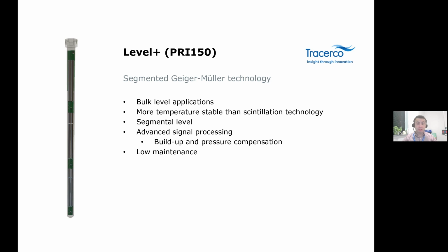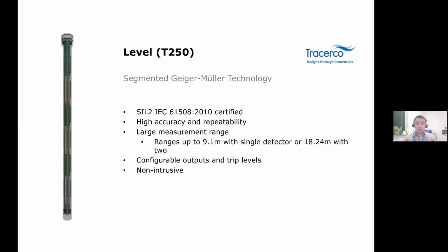Using Tracerco patented technology, the PRI 150 is a breakthrough in level measurement. Unique processing algorithms provide unparalleled insight into the vessel operating condition, monitoring what occurs in the vapor space, allowing extended deposition to be identified. The next generation of our Level Plus includes a SIL2 certification with similar high accuracy and repeatability for applications which have the safety function taken with an instrument.